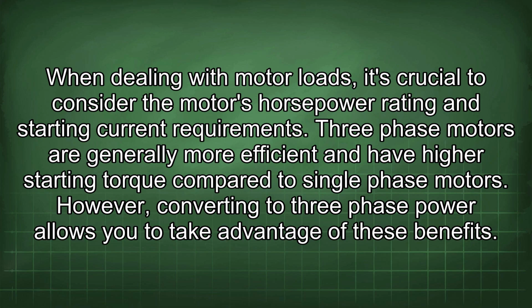When dealing with motor loads, it's crucial to consider the motor's horsepower rating and starting current requirements. Three-phase motors are generally more efficient and have higher starting torque compared to single-phase motors. However, converting to three-phase power allows you to take advantage of these benefits.